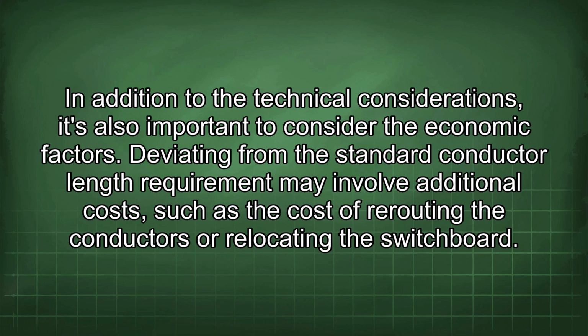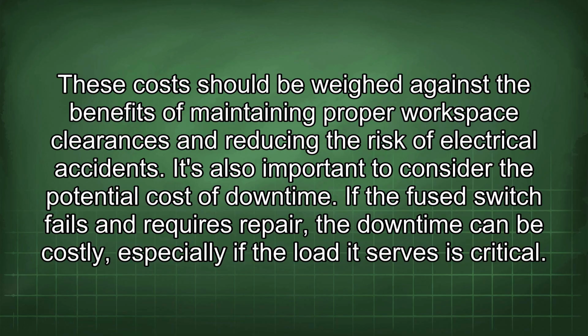In addition to the technical considerations, it's also important to consider the economic factors. Deviating from the standard conductor length requirement may involve additional costs, such as the cost of rerouting the conductors or relocating the switchboard. These costs should be weighed against the benefits of maintaining proper workspace clearances and reducing the risk of electrical accidents. It's also important to consider the potential cost of downtime. If the fused switch fails and requires repair, the downtime can be costly, especially if the load it serves is critical.